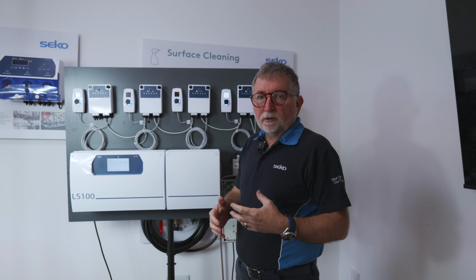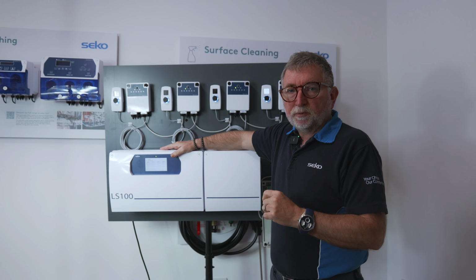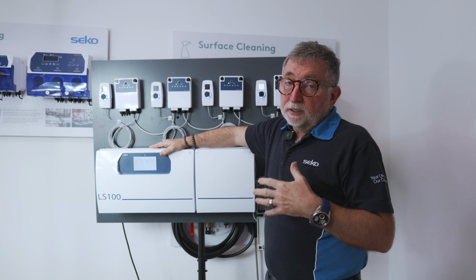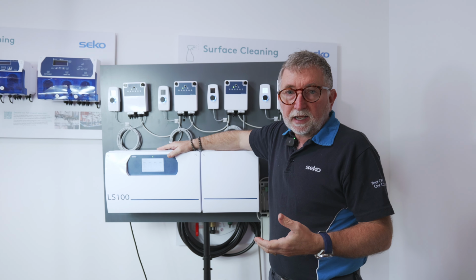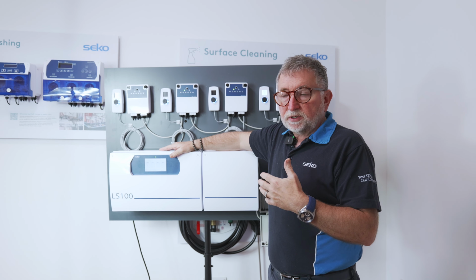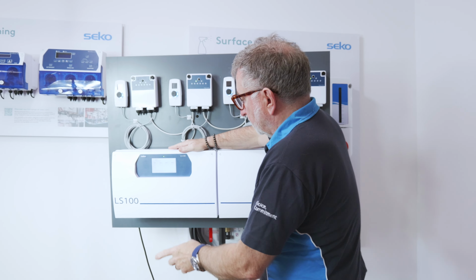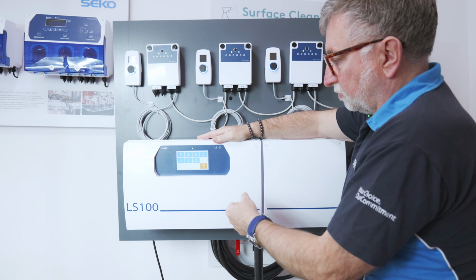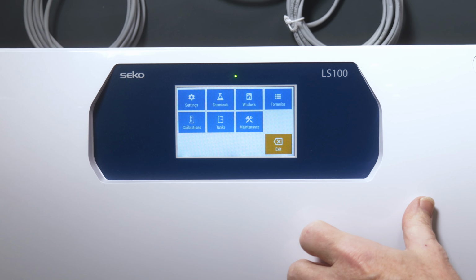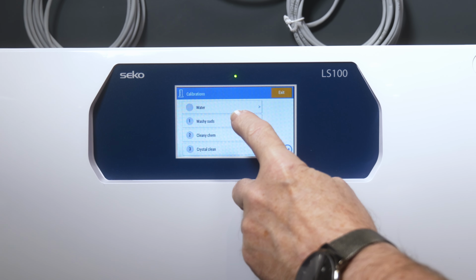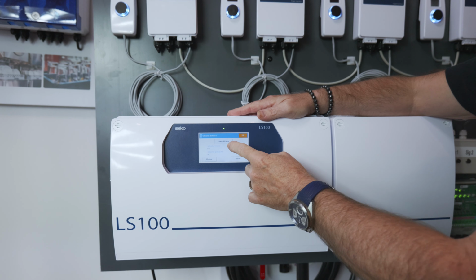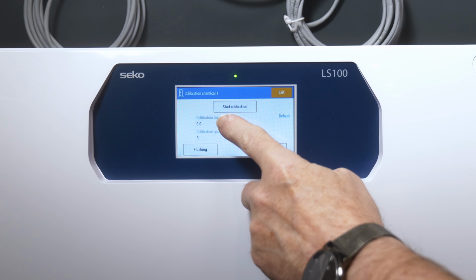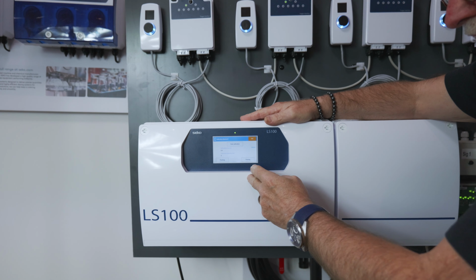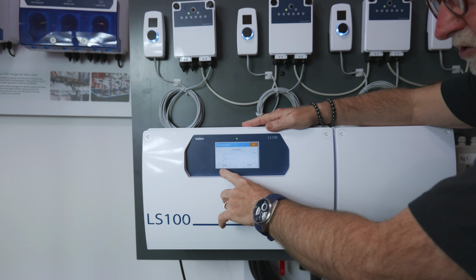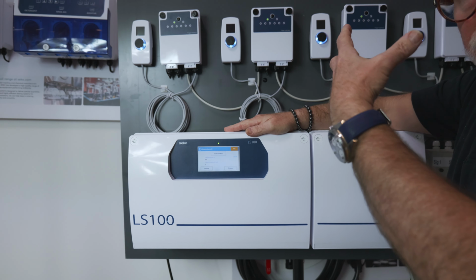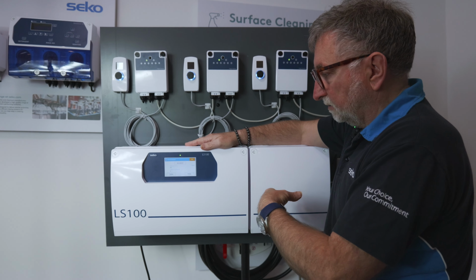So as we mentioned previously, the advanced version of the system does have 2 flow meters, which means you don't have to calibrate the chemicals. Now you can still do this process for statistical analysis and for the flow. So we'll just go through this procedure quickly on the system. So again, by entering the menu on the touch screen, we can go to the calibrations menu. We can select a chemical and we can start the calibration process. When we stop, we can enter the calibration figure and move on to the next chemical. You can also prime in this menu, and you can also flush the system through to get rid of any residual chemical so you can move on to the next one.